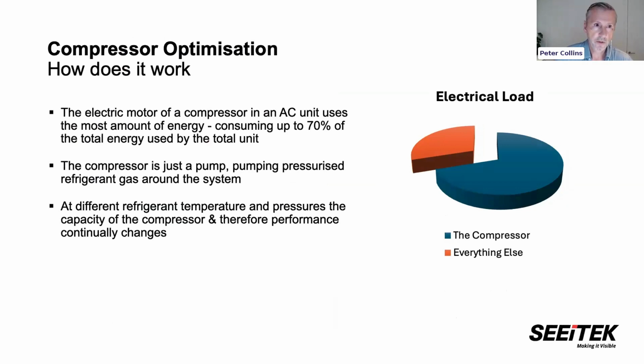The electric motor in the compressor is the highest consumer of electricity in that piece of equipment, whether it's a chiller, refrigeration plant, or heat pump system. Even with new technologies today, we're still looking at consumption of between 50 to 70% of the total energy of that unit. So we're focusing on that compressor today primarily because it is the biggest consumer of energy.